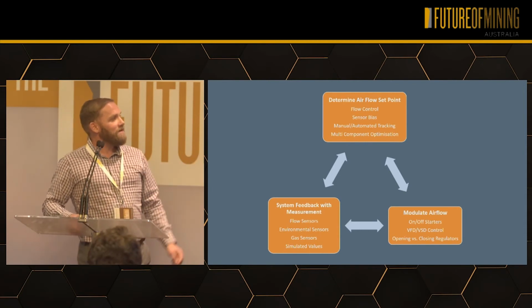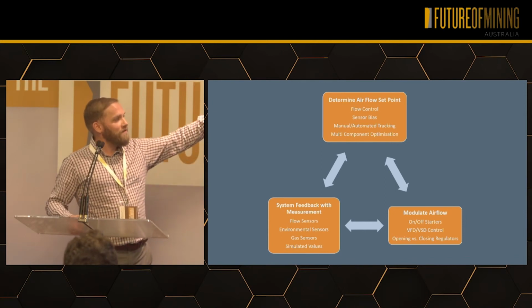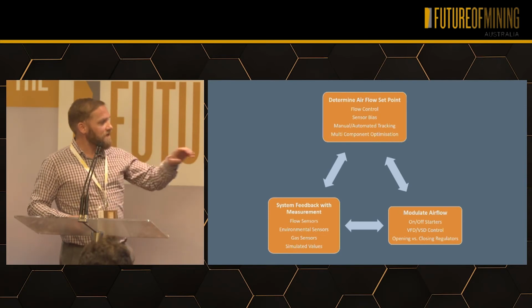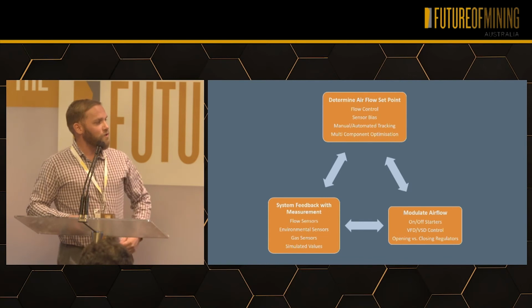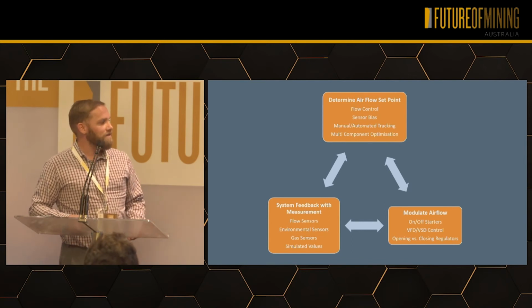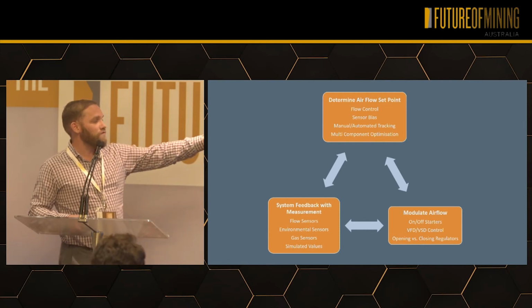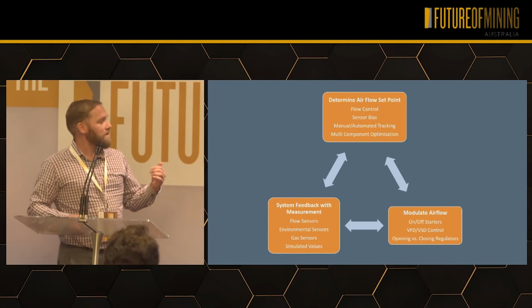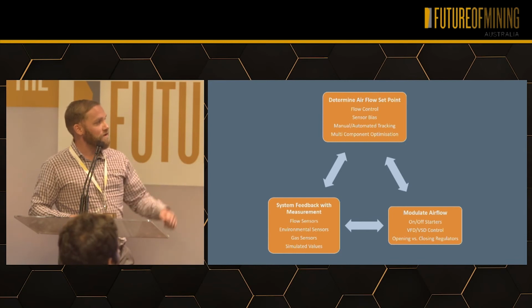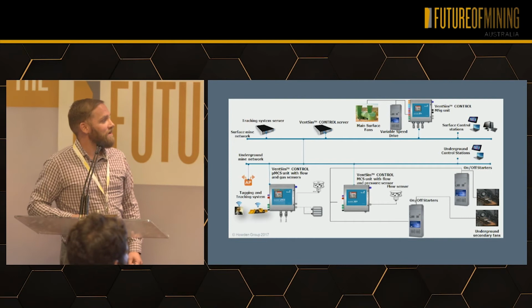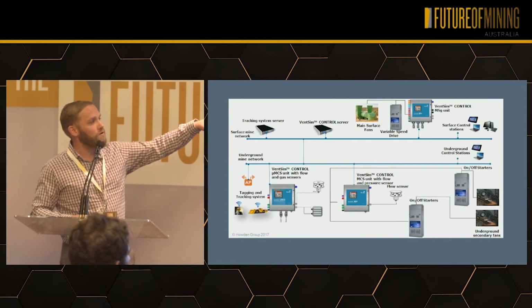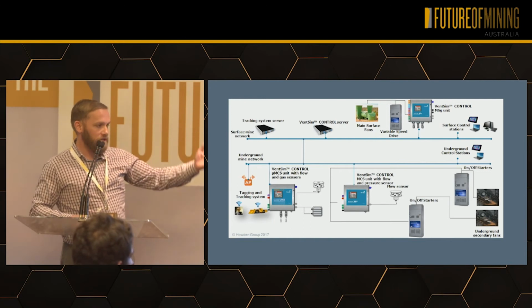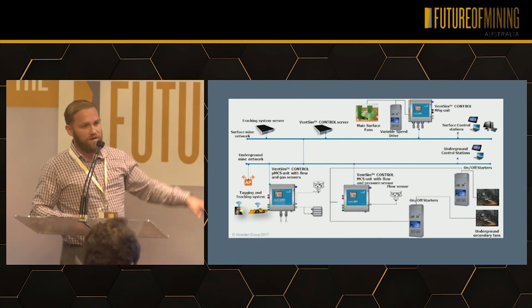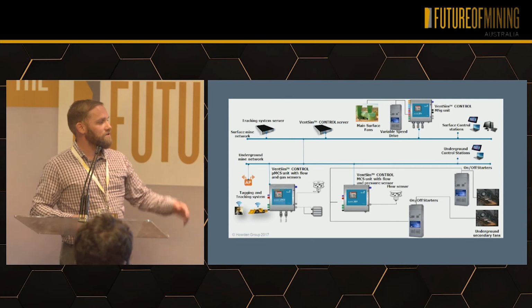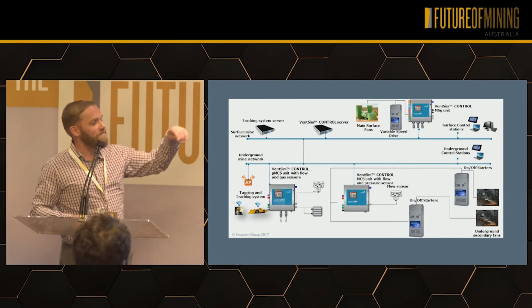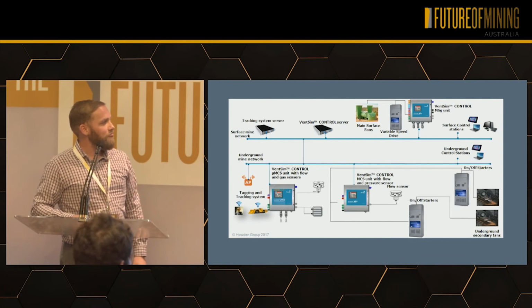This graphic shows the link between the airflow set points at the top and, at the bottom right, the modulation of the airflow with starters, VSD controls, and regulators. Then you've got the system feedback, which is real-time data underground giving that information back up to the software - a typical network with servers and software on top. Using fiber optic network, LTE, or leaky feeder, it can be connected anywhere in the mine, with sensors at key locations and regulators on levels, secondary fans, and primary fans on the surface, tying everything together.